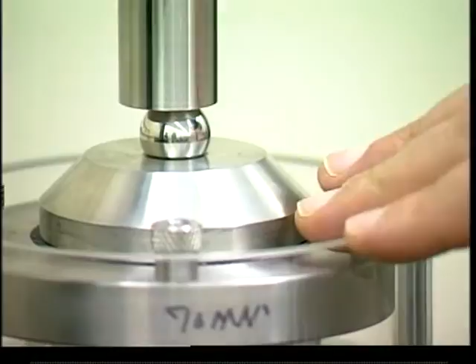So what we're going to do next is everything is going to be controlled through the computer. All right. The next step, what we did here is we set up our consolidation cell with the calibration disc inside. So we're going to load the software, and we're going to run the software to do the machine deformation. How often do you do machine deformation? Once. It's not going to change because the frame is not going to change. Unless you're changing something like a new cell or a different size sample, 2.5 inch or something like that, then you might want to do it. But typically, you only do it once.